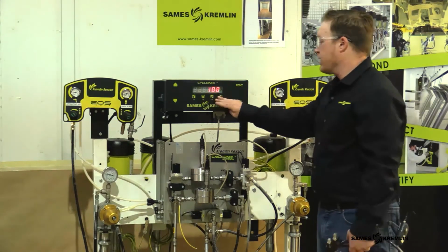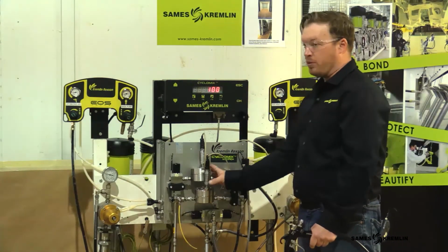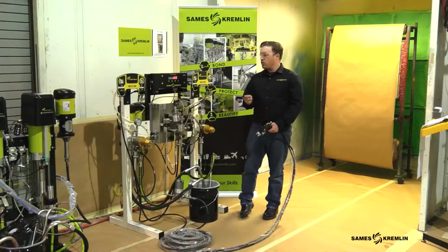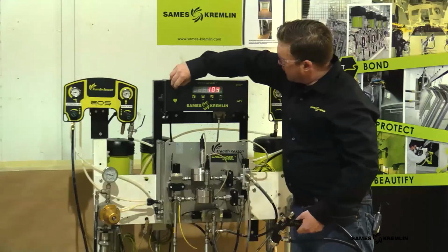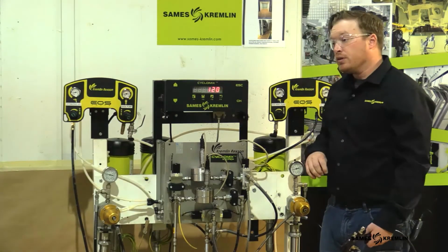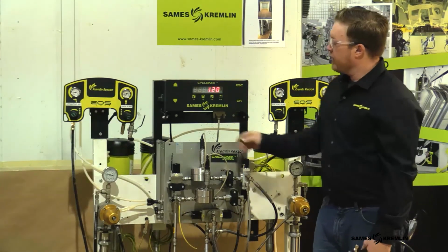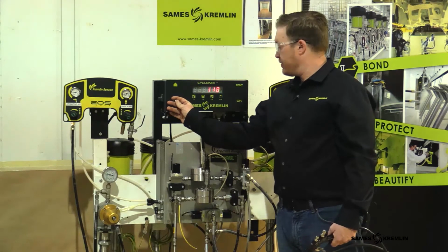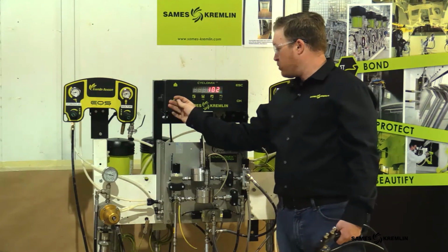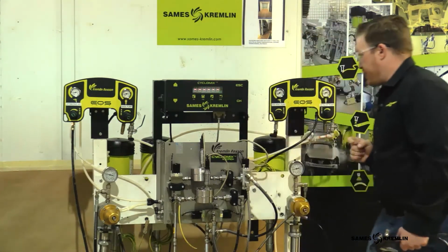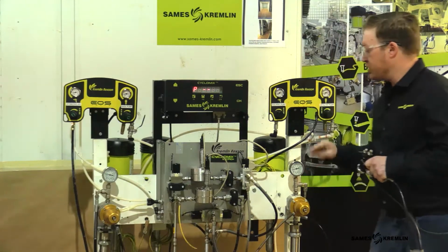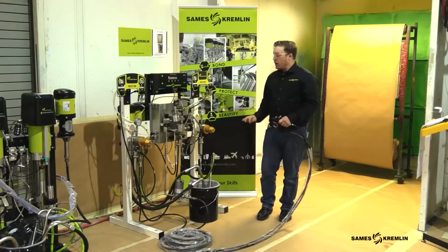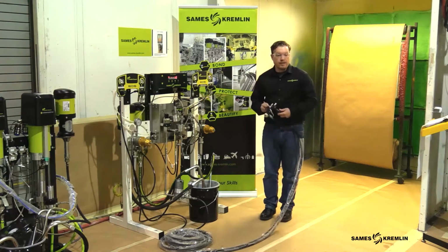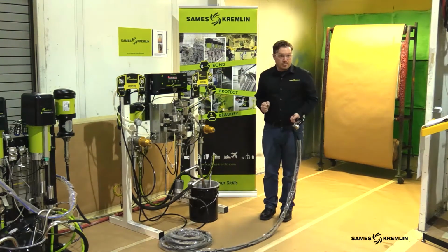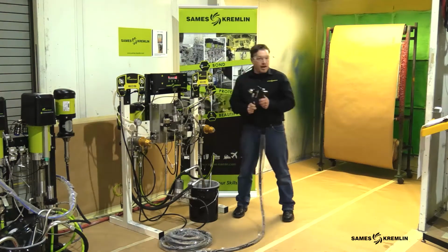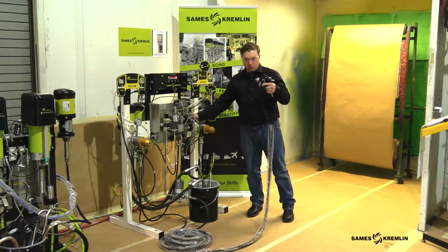Now the 100 is referencing 100 pulses from the flow meter. You can increase or decrease the sensitivity: the larger number is going to decrease the sensitivity of this parameter, and the smaller number is going to increase the sensitivity of this parameter. And what we have this P12 for is in certain situations when this machine is being tied into an automatic system, certain automatic systems are not capable of delivering us a gun-on signal. By gun-on signal, I'm referring to that flow switch signal.